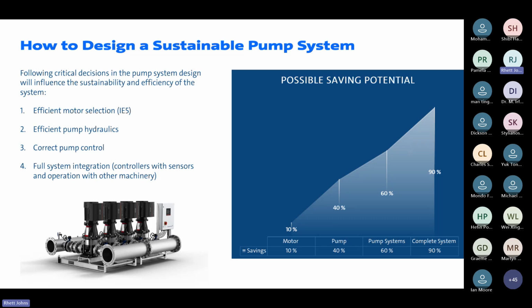And then looking at pump systems, we're looking at multi-pump control, where we've got some sort of control standard on it, like a pressure control or temperature control value that we're trying to target our pumps running towards. And then we look at complete pump systems. When we talk about complete pump systems, we can go up to 90% potential savings. In these sorts of systems, your pump controller, like you see in the pumps at the bottom left, is working within the wider network of the system, communicating with machinery such as the boilers and the chillers, to run the pump only at the required flow or pressure demand that these systems have. So that's your 90% of potential savings within the system.